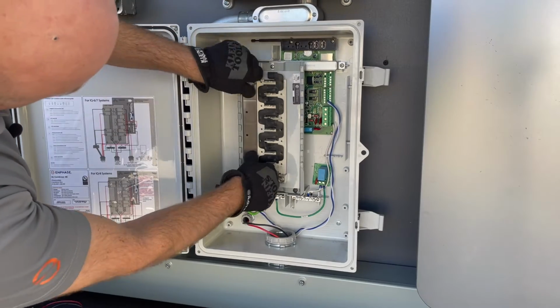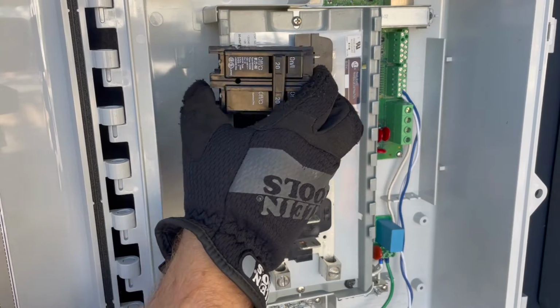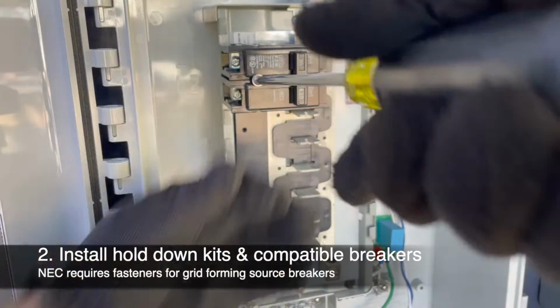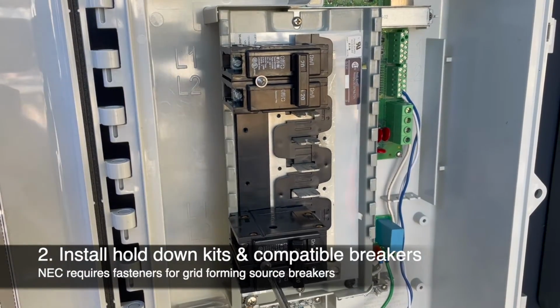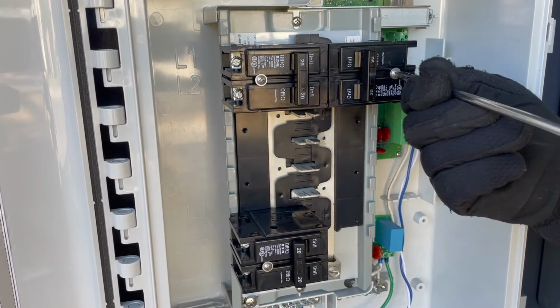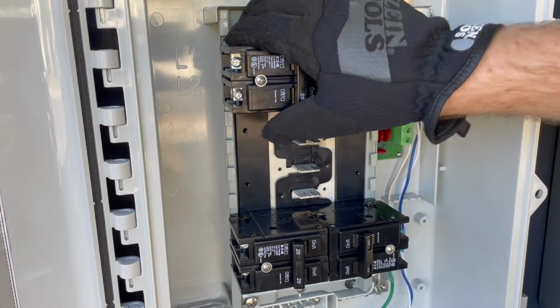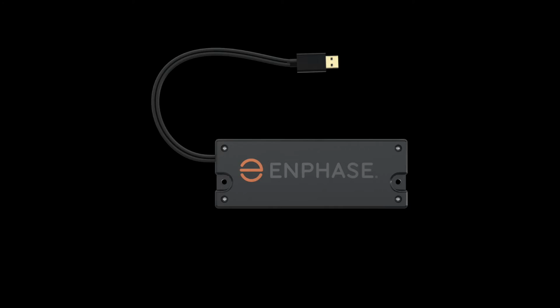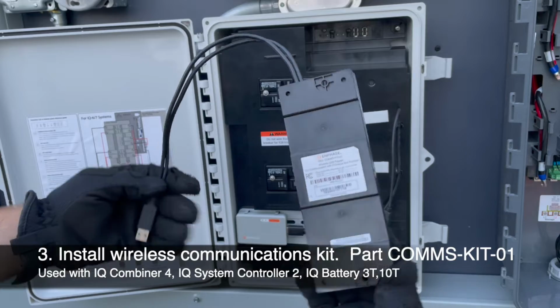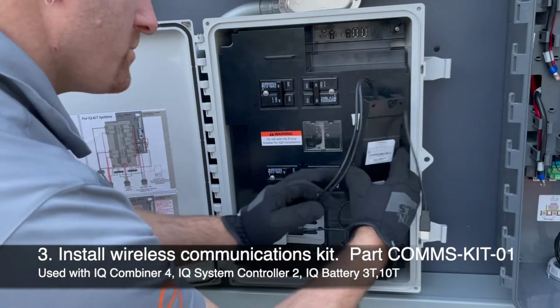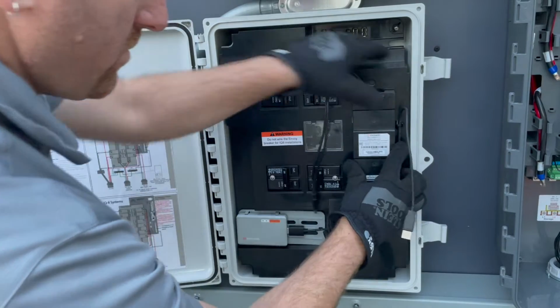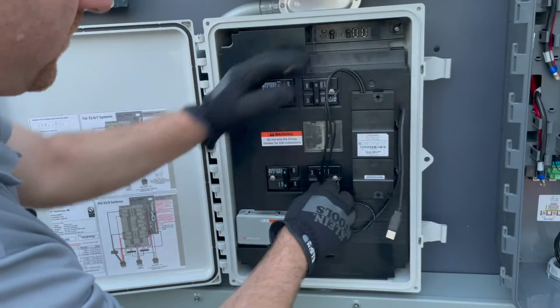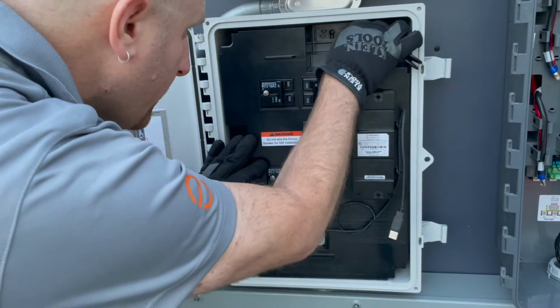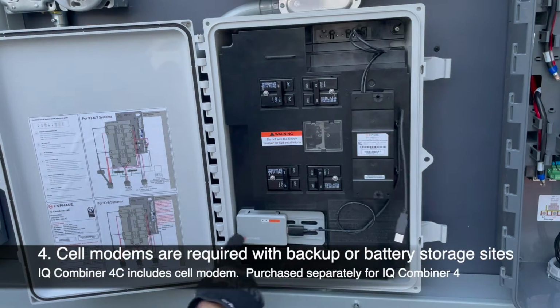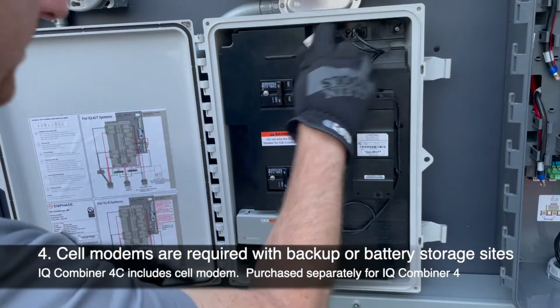Since this is a backup capable site with IQ8 microinverters, be sure to install breaker hold-down kits with compatible breakers. The IQ Combiner 4 can support 4 hold-down compatible breakers. Sites with a system controller or battery storage will require the Enphase Wireless Communications Kit installed here. A cell modem is required for backup or battery storage sites.